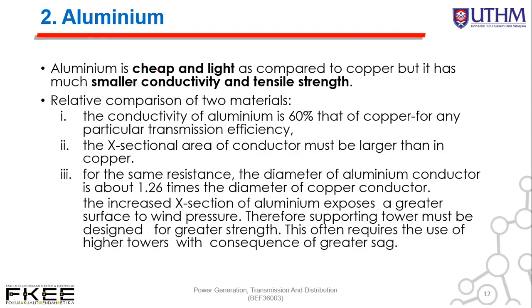Second is aluminium. Aluminium is cheaper and lighter compared to copper, but it has smaller conductivity and smaller tensile strength. The conductivity of aluminium is 60% that of copper. The cross-sectional area of aluminium conductor must be larger than copper for the same resistance. The diameter of an aluminium conductor is about 1.26 times the diameter of a copper conductor. The increased cross-sectional area of aluminium exposes a greater surface to wind pressure, therefore supporting towers must be designed for greater strength.